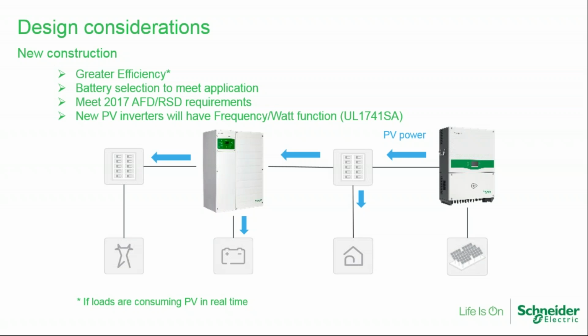AC coupling. Some of the old ones, on the other hand, the Fronius comes to mind. They had a method that they used for detecting the grid where they sent out a pulse. It was called impedance checking. They would send out a current pulse into the grid, and if the grid was connected, it would get absorbed and nothing would be reflected. But if an inverter was connected, that's a high impedance output. And unless you had loads on in the system that could absorb the pulse, it would get reflected back, and the Fronius would tell you that it's not connected to the grid and wouldn't allow production.